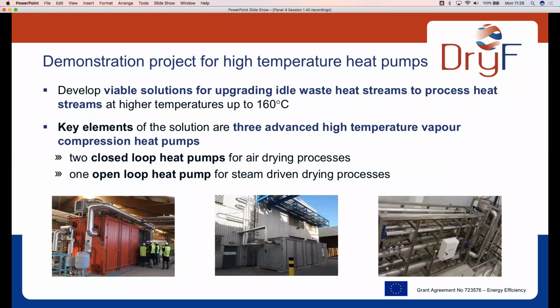I will speak about our demonstration project, Dry Efficiency. Within this project, we develop high temperature heat pumps that are able to supply process heat at 160 degrees C. We focus on drying processes because drying processes require a lot of energy and they're usually carried out with fossil fuels. Within the project, we develop three different heat pumps. Two of them are closed loop heat pumps that are used for drying with air. The third heat pump is an open loop heat pump, which is used for a steam drying process. The open loop heat pump is a mechanical vapor recompression system, and it will be used in a sludge dryer. On the pictures below, you see the three demonstration plants.